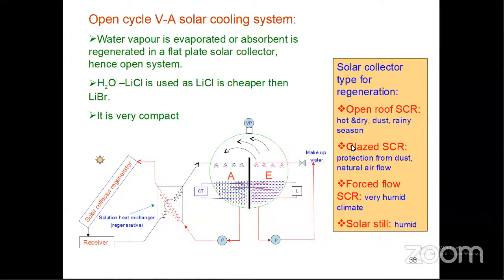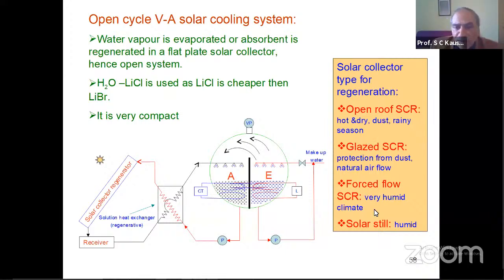I don't know. Anyway, for improving the cooling capacity and COP, there are different designs of solar collector regenerator. One is the roof surface. I mentioned that for a building, but it is suitable for hot and dry climate because the maximum rate of water mass evaporation can take place in hot and dry climate. But in a dusty, rainy season, it is contaminated. So another option is a glazed solar collector regenerator. It will protect from dust, and we may provide a natural airflow to increase the rate of water evaporation.